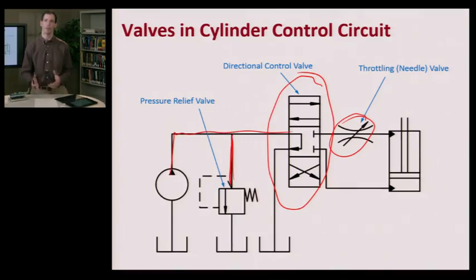So we exceeded the pressure of the pressure relief valve, cracked the spring open, and then had our additional flow go across that pressure relief valve, therefore slowing down the hydraulic cylinder.